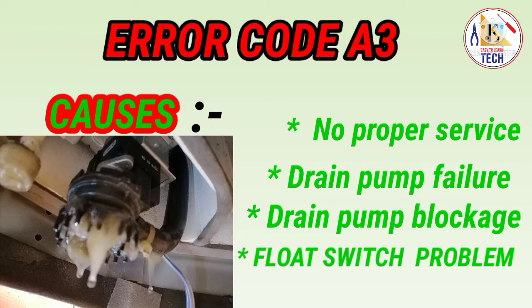In most cases when you see error A3, you can directly open your cassette unit and check the drain pump. If proper servicing has not been done, a lot of dust and dirt can accumulate in the drain pump, which can block it. There will be no proper water drainage from the cassette unit and you will get this error. Second, if the drain pump has failed or is shorted, you will also get error A3.